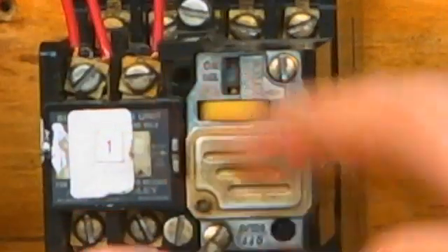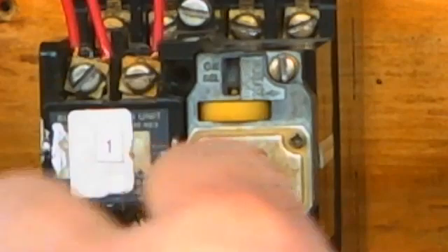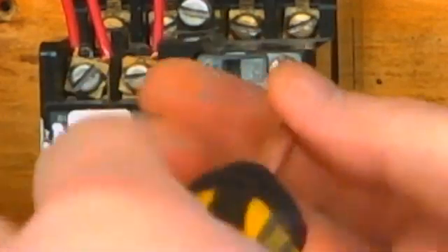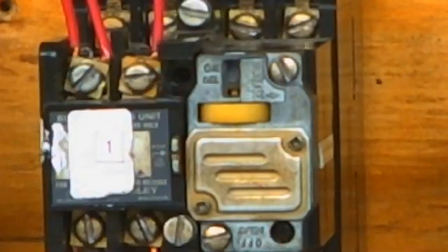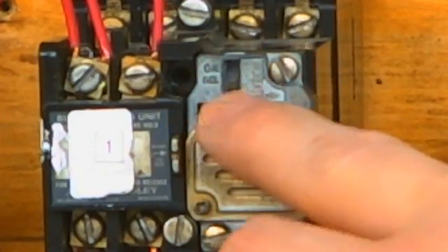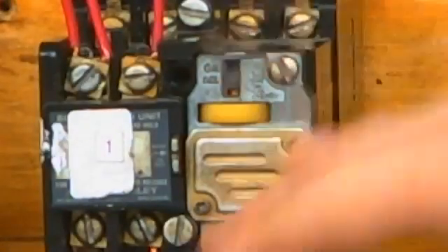Look, now it says on delay. So what happens with the on delay timer? They will turn on in 3 seconds. I push the button, the coil, you will see this thing pull in, but it's not going to change state until the timing is done. So on delay timer, the timing function happens when the coil turns on. Off delay timer, the timing function happens when the coil turns off. It's still set on the same timing because I haven't moved this dial. It's about 5 seconds or whatever it is.